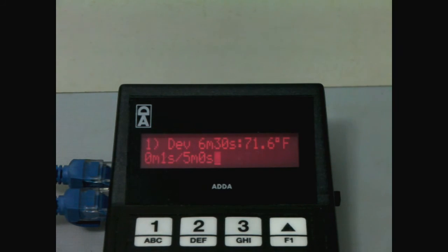Once the develop step is over, it continues to the other steps as programmed. No temperature compensation will take place as long as these steps are not programmed as develop steps. You can leave the probe on the tank until the whole process countdown has ended.